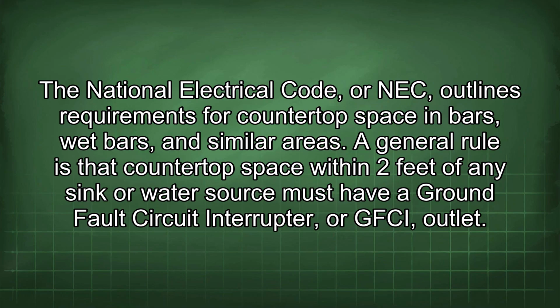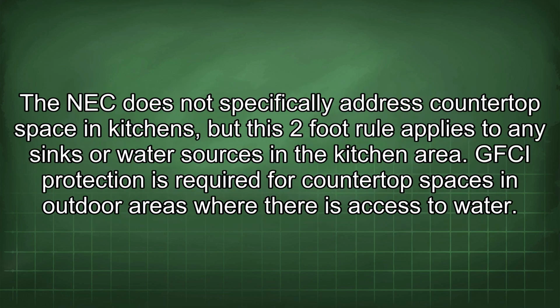The National Electrical Code, or NEC, outlines requirements for countertop space in bars, wet bars, and similar areas. A general rule is that countertop space within 2 feet of any sink or water source must have a ground fault circuit interrupter, or GFCI, outlet. The NEC does not specifically address countertop space in kitchens, but this 2-foot rule applies to any sinks or water sources in a kitchen area.